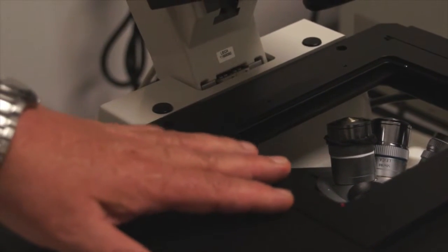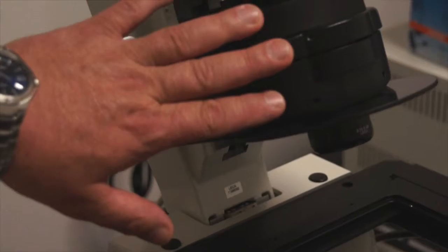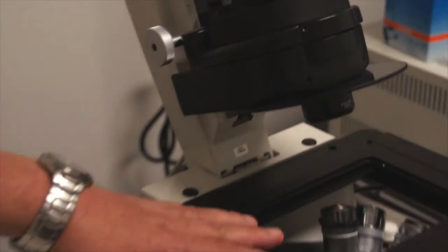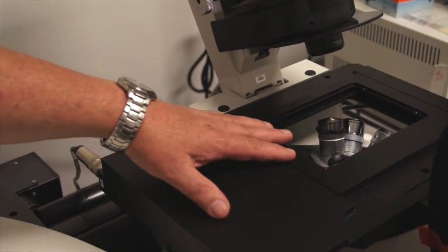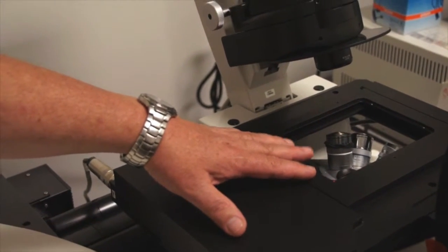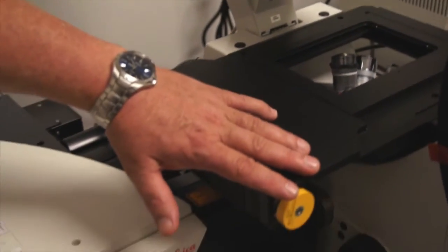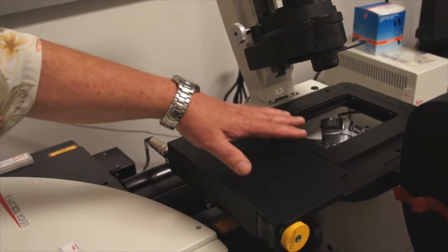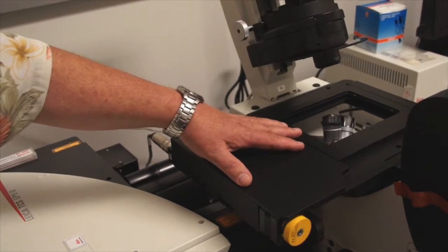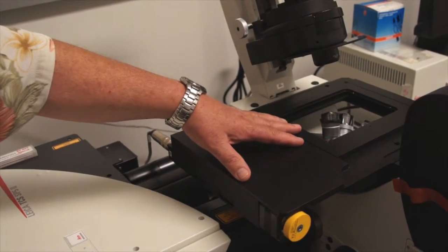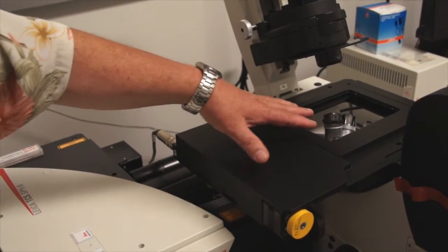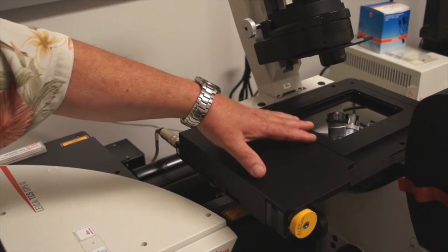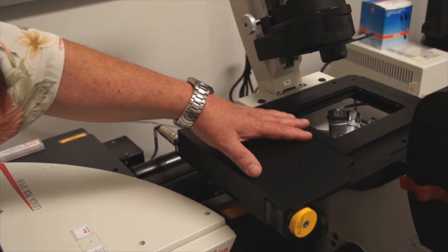And so that's another important reason why the condenser has to be rocked out of the way, because when you initialize the microscope, the computer will drive the stage in X and Y to its endpoint because of the motors that are on each axis of the stage. So be aware that this is a robotically controlled motorized stage which can injure your fingers. You could actually lose a finger if you put your hands in here while the stage is moving. So when the stage is moving, keep your hands and everything free and clear from the stage.